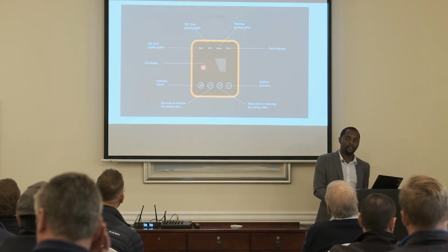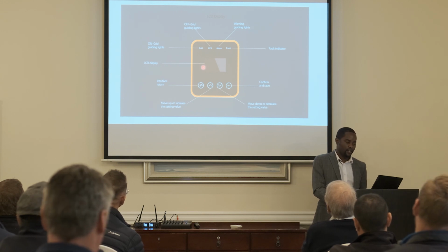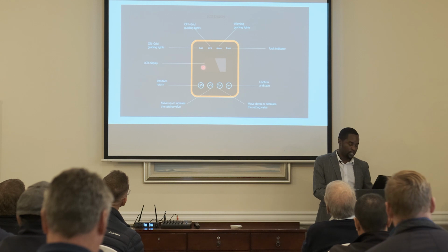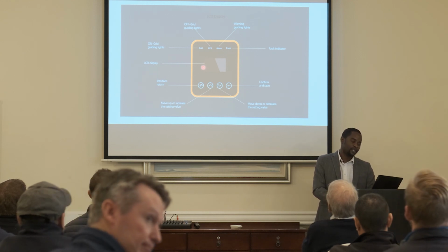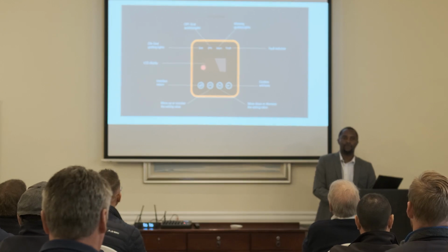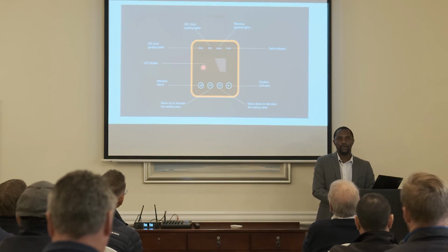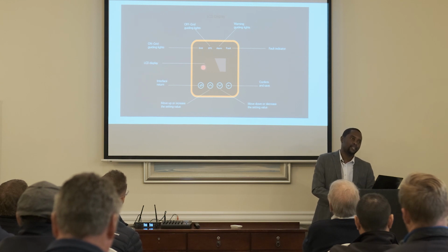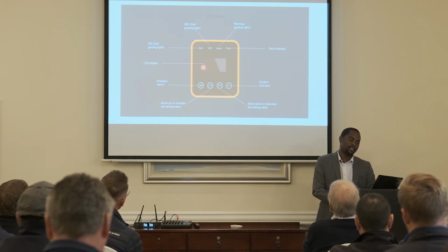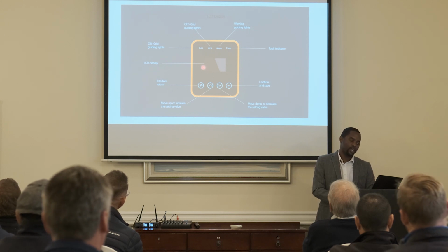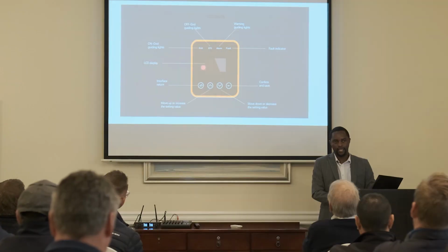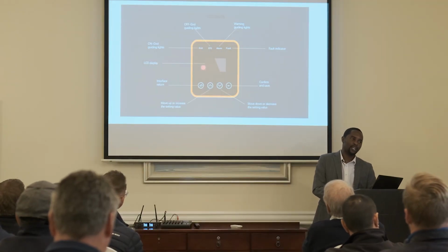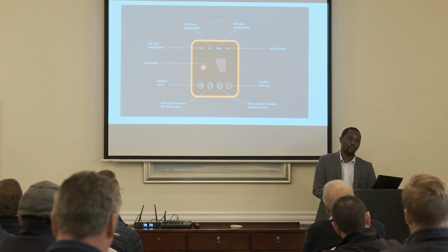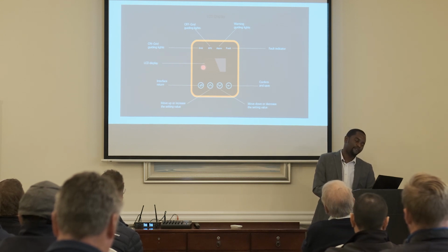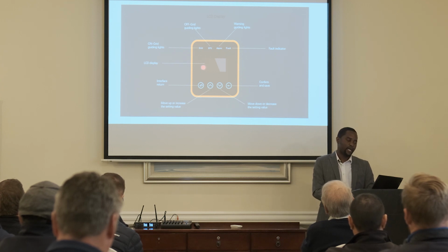So the screen, the display, the HMI, is a soft touch screen. Then we've got 4 LEDs that can be on, which are the grid, the EPS, the alarm, and the fault. The grid is just showing you that grid is available. When it's not available, then it's off. Then the EPS is your backup. It's showing you that your inverter is in backup or it's ready to be in backup in case you lose grid. Then the alarm is giving you a warning that does not stop the inverter from working. Then the fault, these are warnings or faults that stop the inverter from working. So if you've got a fault on, you need to attend to it before the inverter can work. But an alarm is just telling you that you need to check this, but still the inverter will be working.